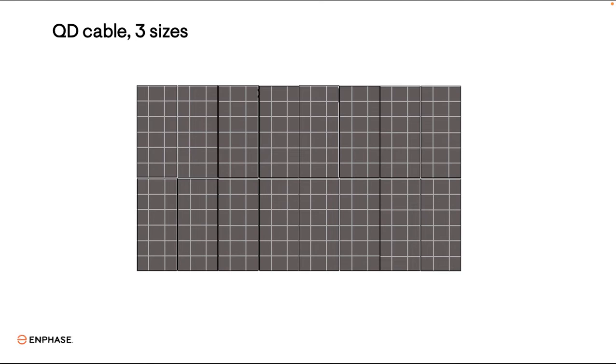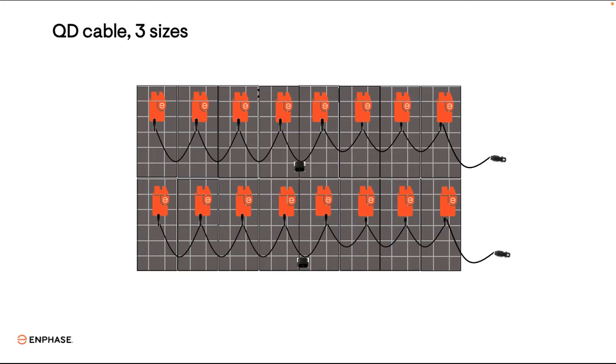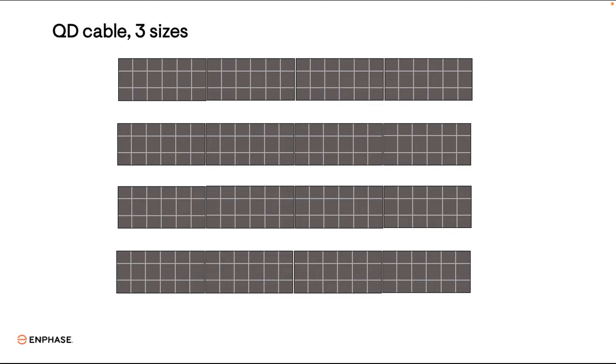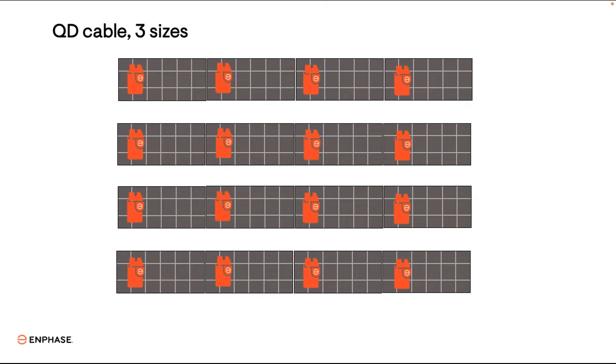Portrait cable is intended for arrays where the panels are butted against one another in portrait orientation with no spacing between east and west panels. Inverters need to be relatively close to one another in order for the connectors to be able to plug in to the next inverter. Landscape cable is for ballasted arrays in a traditional landscape orientation relative to the roof.